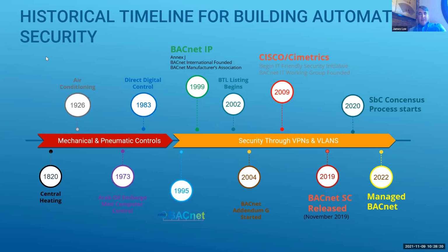The danger was that with BACnet SC on its own, we could end up in a situation where we could undo 30 years of open systems by having proprietary tools and management structures on top of BACnet SC that would lock things up. So what we've done with largely the most proactive and largest players in the industry is work on a standard over the last 2 years. And it's actually a framework. And we call that framework Managed BACnet.